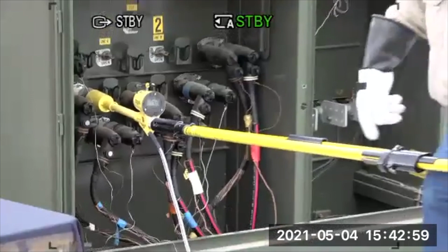So what we're going to do now is some phasing off capacitive test points. It's very safe to phase off capacitive test points. Obviously, you're just looking at about 10% of the nominal voltage. And how we're going to do this is kind of cool because this tool is so accurate. What we're going to do is go phase to ground first off the capacitive test points of these elbows.